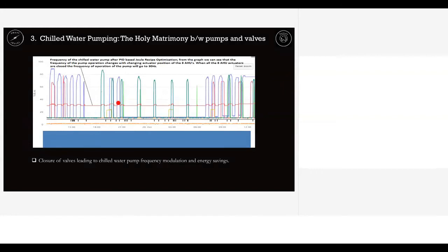That red line is actually the frequency of the chilled water pump. It is not a constant speed pump, it is a variable speed pump that can be operated on VFD. So when the valves open, that means the pressure in the line has come down, and my pump frequency increases. When the pressure in the line is back to normal, the pump frequency comes back. So as per the opening of a valve on the fifth floor, my pump on the ground floor is able to understand that and take an action.